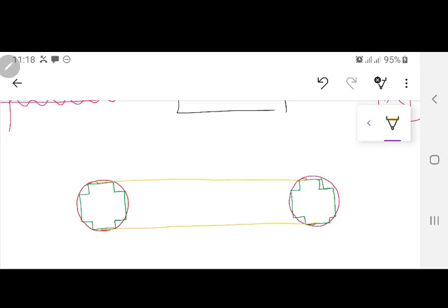Comparing the perimeter of a square versus the perimeter of a circle, the length of the winding reduces, and so the resistance of the winding reduces. This was the main and first reason. This is actually 90% of the reason you make the core circular, because the winding on it will have less perimeter or circumference.